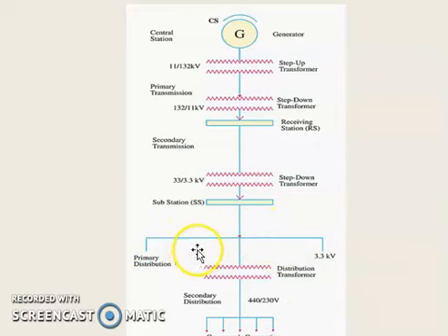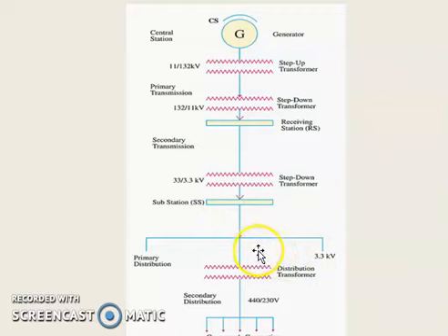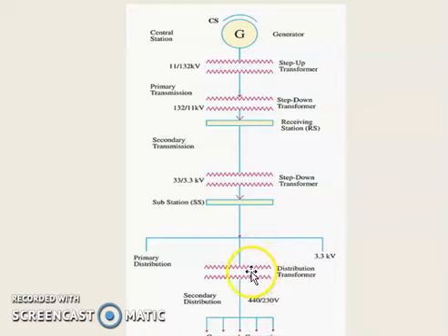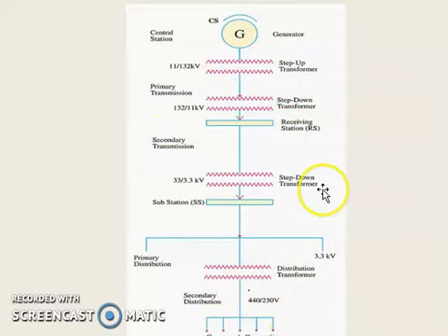From the substation, we have primary distribution and secondary distribution. At primary distribution, voltage is distributed at 3.3 kV, 6.6 kV, or 11 kV. Bulk consumers like factories, institutions, and hospitals are directly served at 11 kV. At the distribution substation, voltage is stepped down to 440 V or 230 V for secondary distribution, which is connected to the consumers. This is the single line diagram representation of the power system.